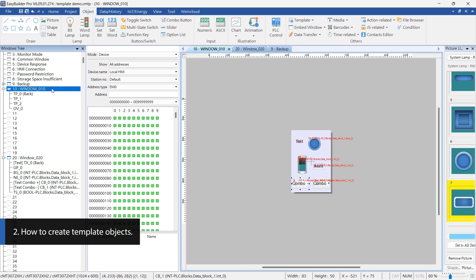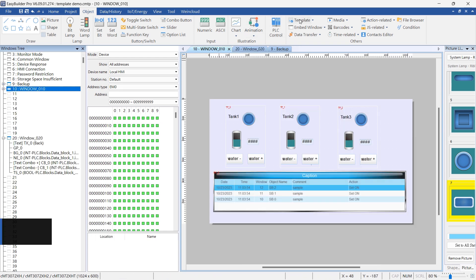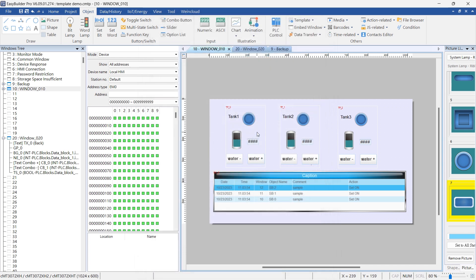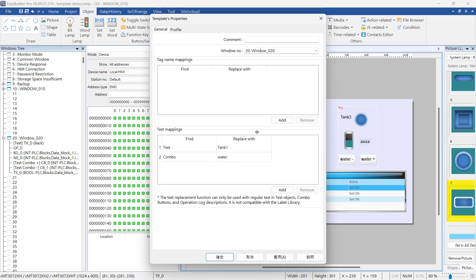Return to the main display window, Window 10, and click Template in the toolbar to add a template object. Clicking on the template opens a setup window where you can define tag name mapping and text mapping rules for a template window. In this example, three template objects have been added. For the first template object, let's keep the tag mapping table untouched and only configure the text mappings.